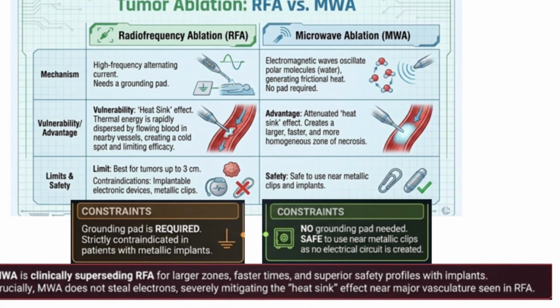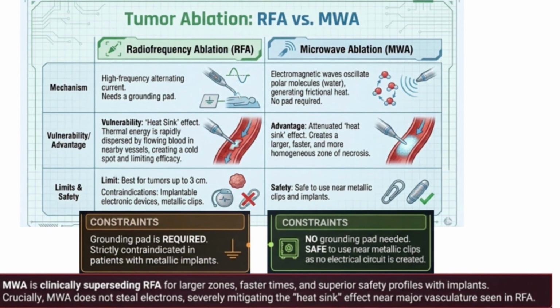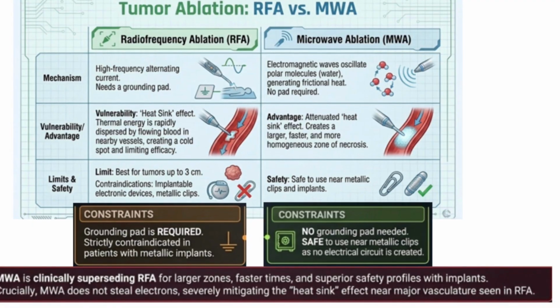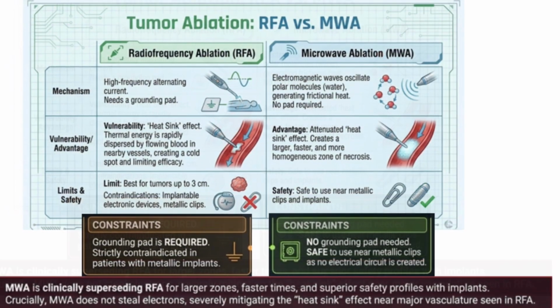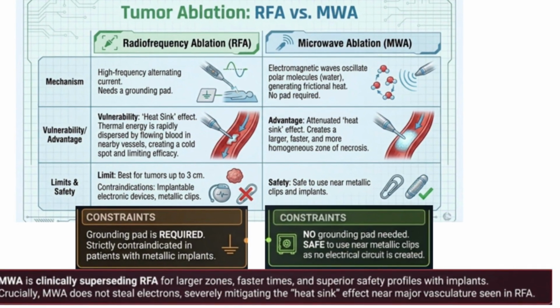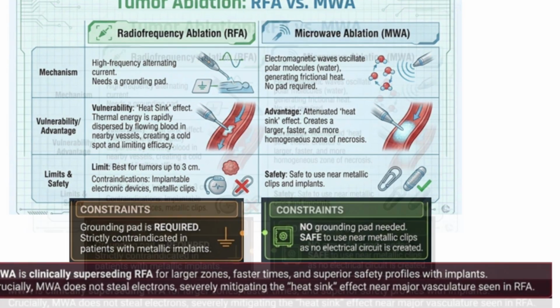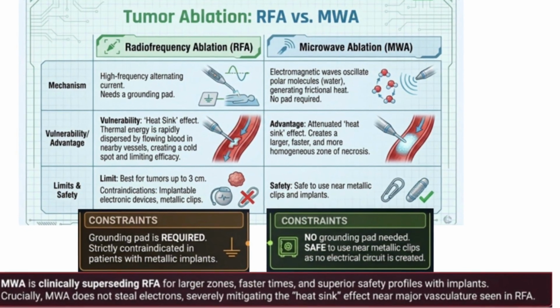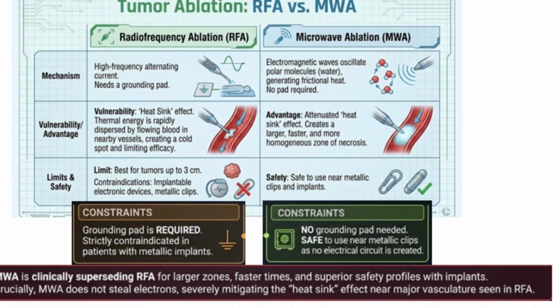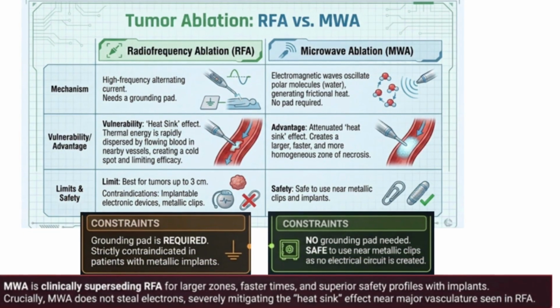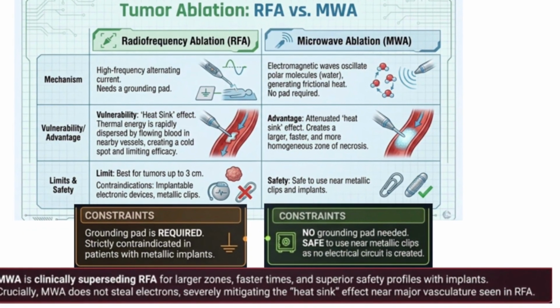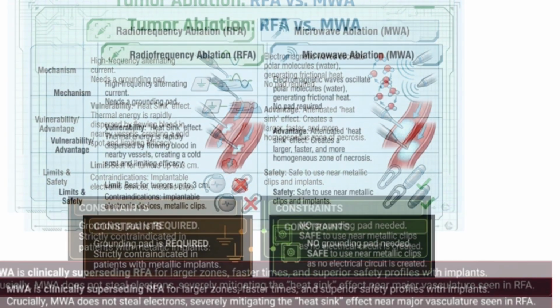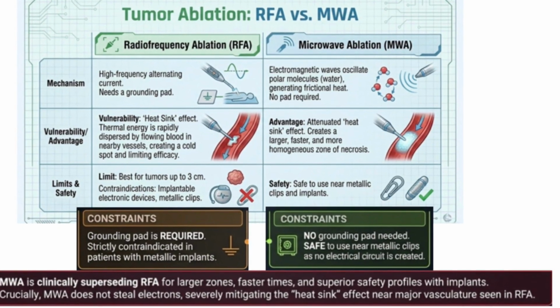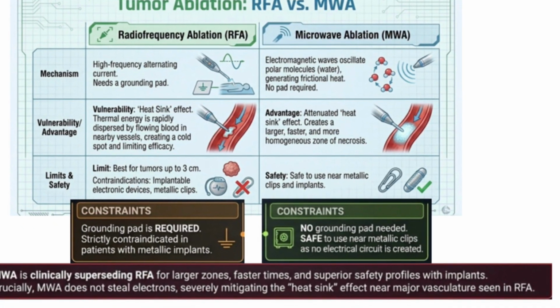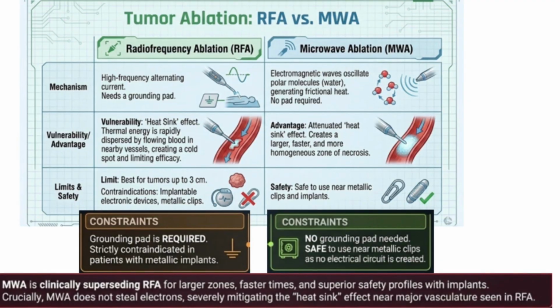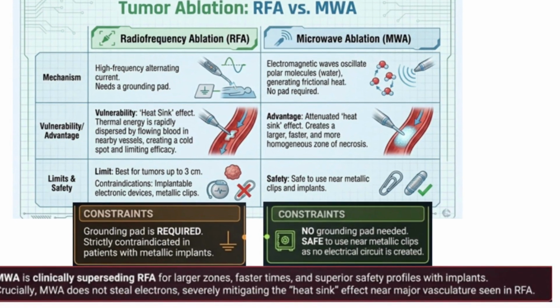In microwave ablation, electromagnetic waves oscillate polar molecules, that is water, generating frictional heat. There is no pad required. The advantage is that it is less affected by the heat sink effect and creates a larger, faster, and more homogeneous zone of necrosis. It is safe to use near metallic clips and implants. The advantages are that no grounding pad is needed, and it has no electric circuit to be created.